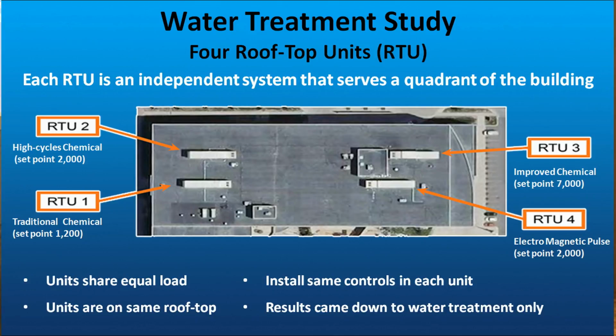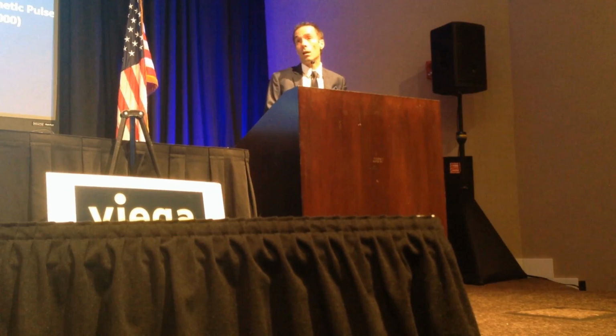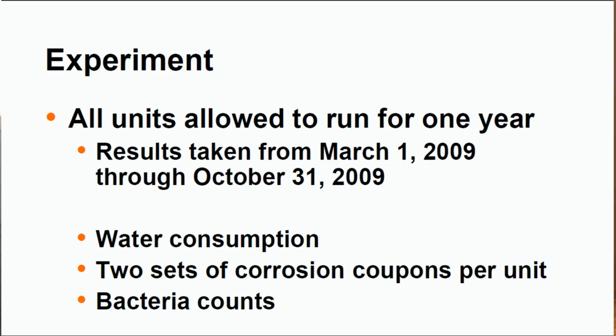Units were on the same rooftop - this is actually an aerial view of the rooftop. You can see the cooling towers there in the different quadrants. We installed the same controls on each unit, and so the results came down to whether the technologies could maintain system integrity, and which one saved the most water. When the results started coming in - again, all the units were allowed to run for 1 year, which was the cooling season for them - they measured water consumption, 2 sets of corrosion coupons, and bacteria counts.